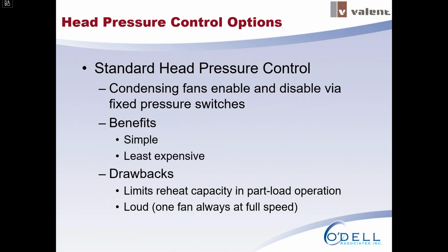The baseline that we're going to compare to is what we just call standard head pressure control. And that's where your condenser fans are turned on or off based on pressure switches. So the benefits is it's pretty simple and not very expensive. The drawbacks is you lose reheat capacity at part load because more of your hot gas is being sent to the condenser because the fans are at full capacity. And it's also very loud. So if you can't modulate your fans down, your fans are at full speed, you're going to have the highest sound.